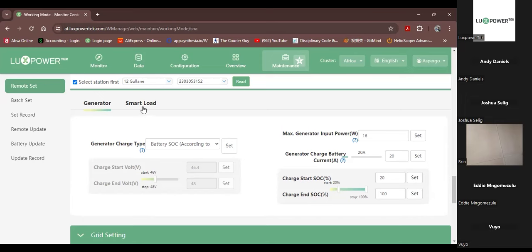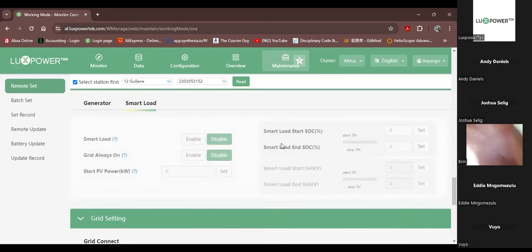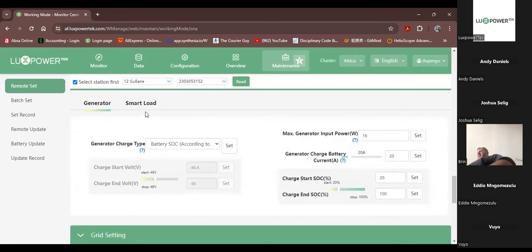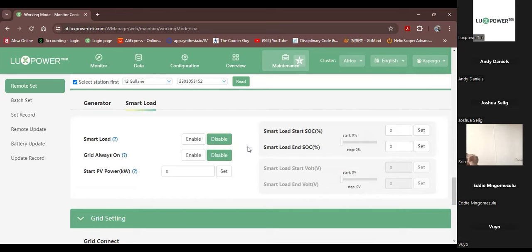Right, so the next tab here that we have is the smart load tab. Now, we have preset this. The machines that have the TP on the generator port, which are the new machines, will be enabled. You'll be able to enable the smart load function. So what does smart load mean? Smart load means that we can turn the generator port into either a port that receives power from the generator, or we can turn it to a smart load port. A smart load port simply means an auxiliary output port.